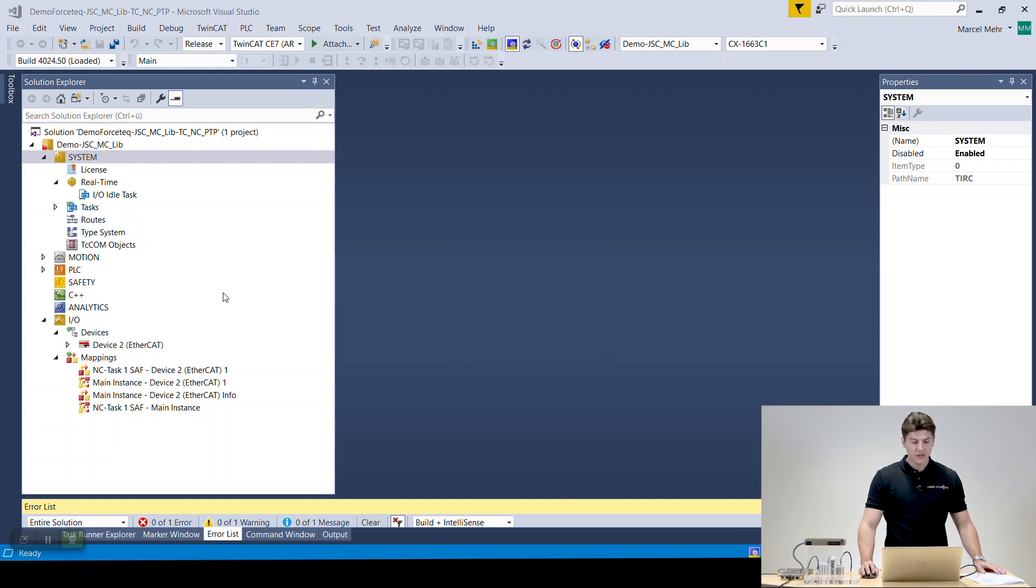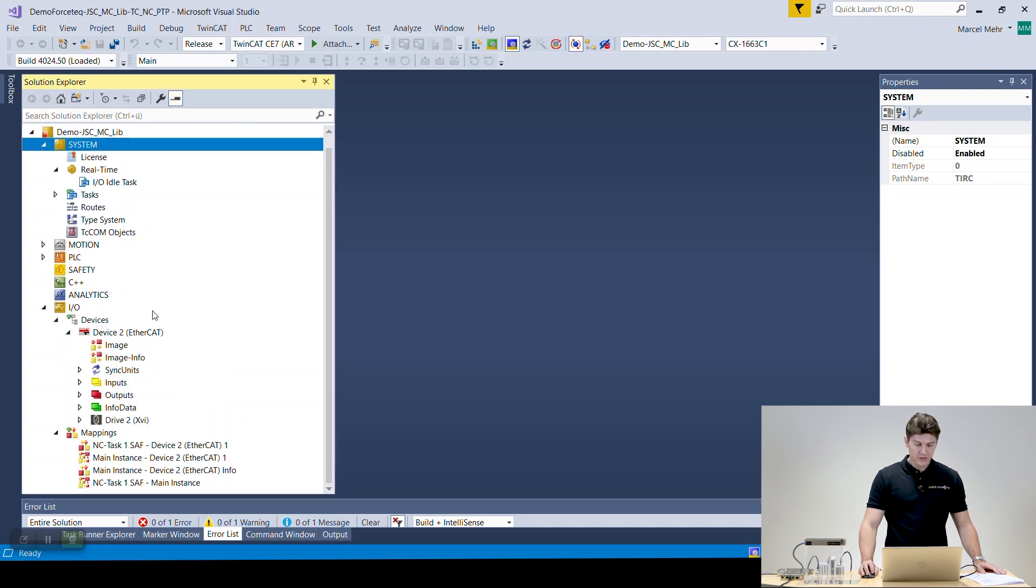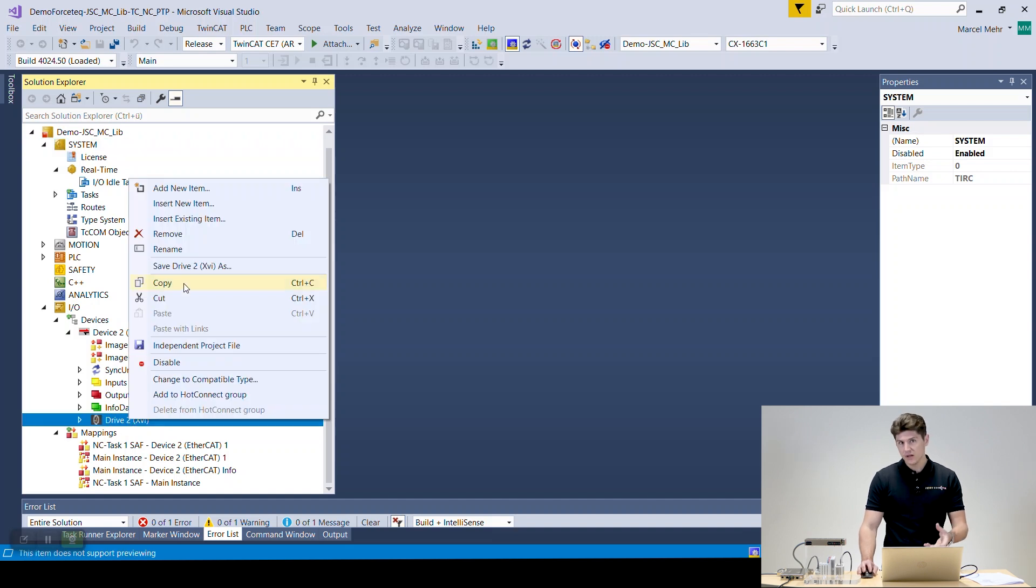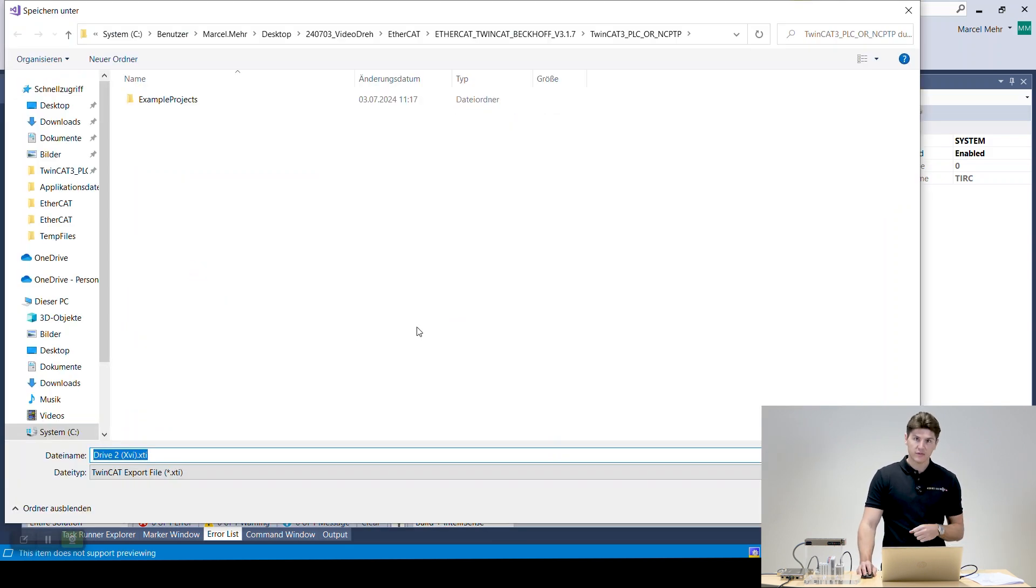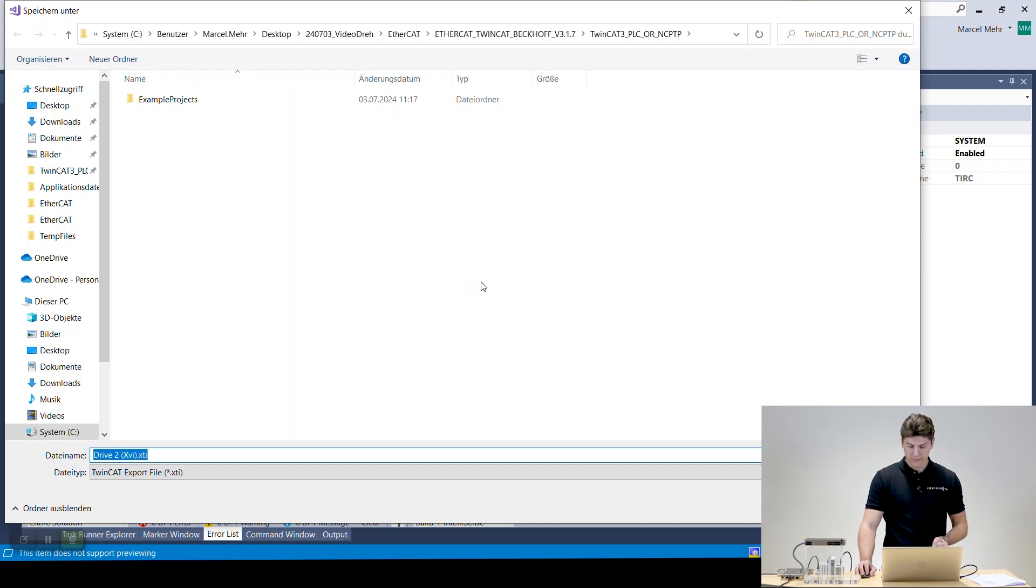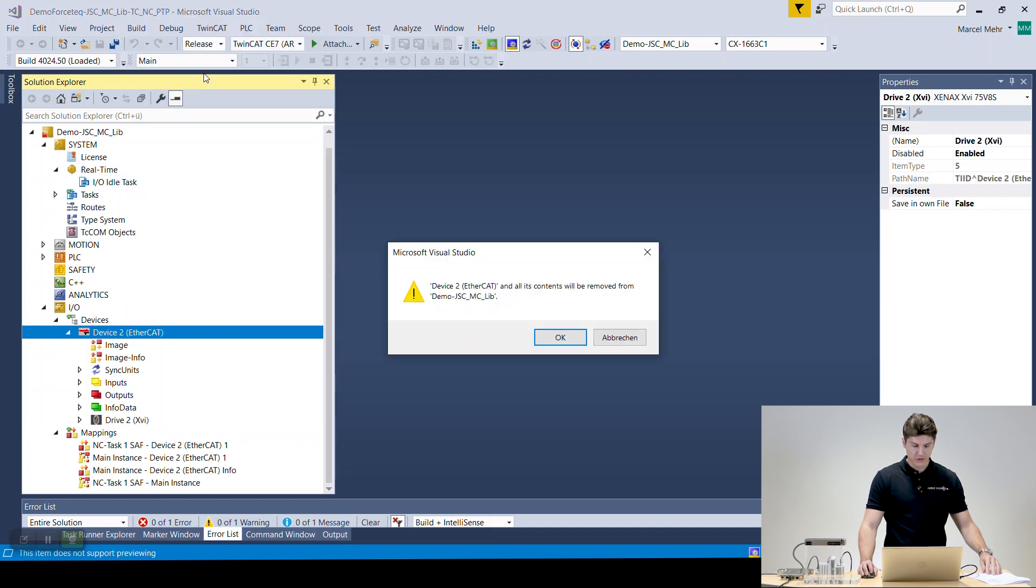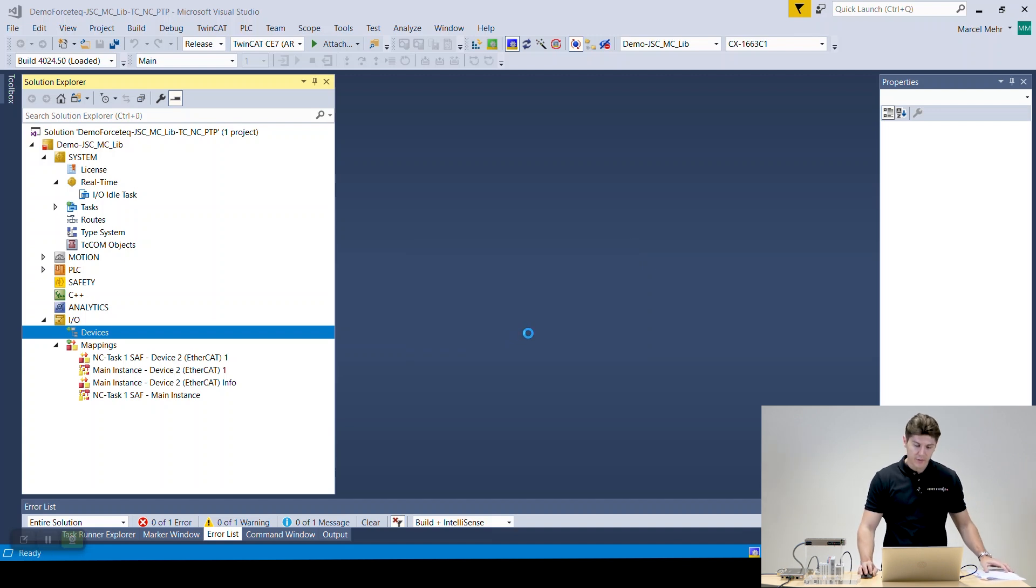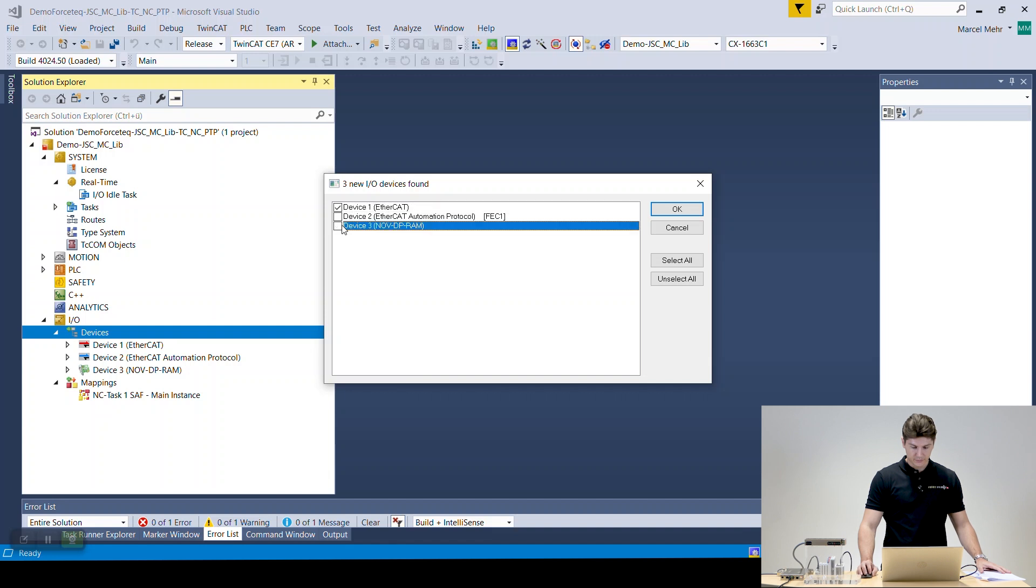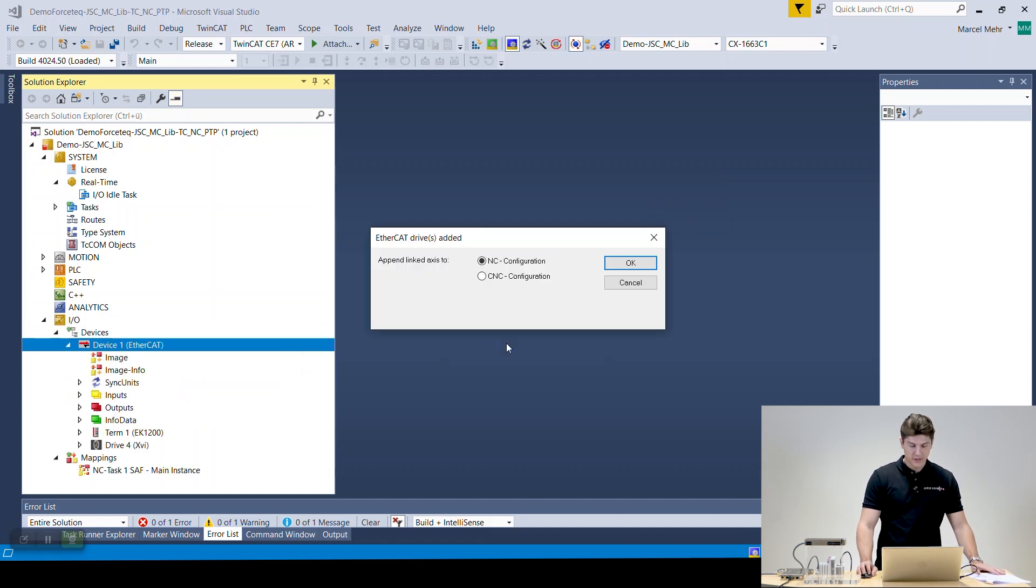So now here on the demo project on the left side you see the devices. What we're going to do is as it's preset we're going to save the drive because all the links of the PDOs are already done, so later on we don't have to do it manually. If you want to do it manually by hand you'll find every step in the manual as well. So we're going to save it and then we're going to delete the whole device. And after that we're going to scan for new ones and it will find the whole system we have here. Very important, we just want to scan for the EtherCAT devices. Scan for boxes. Here we cancel it and we don't want to run it.